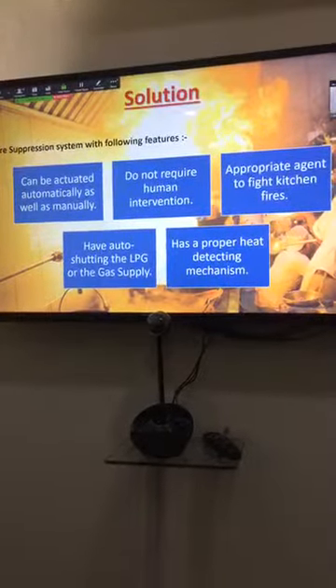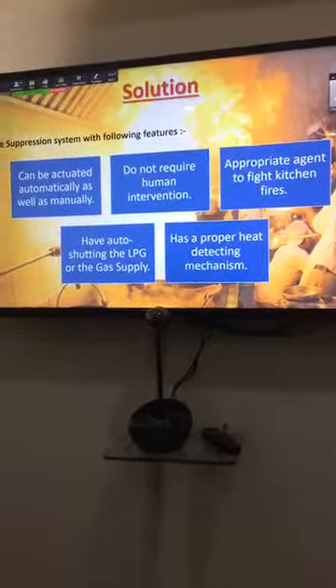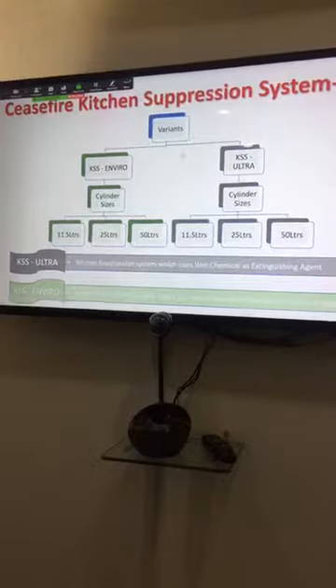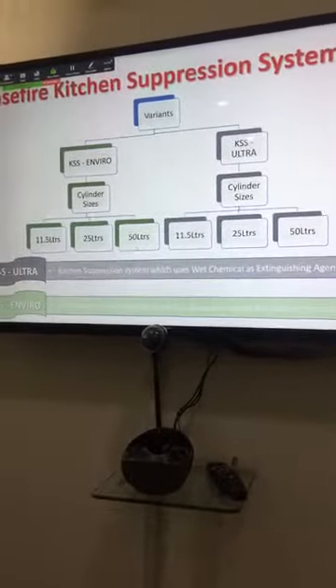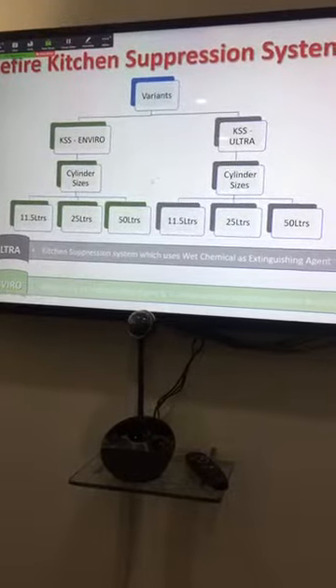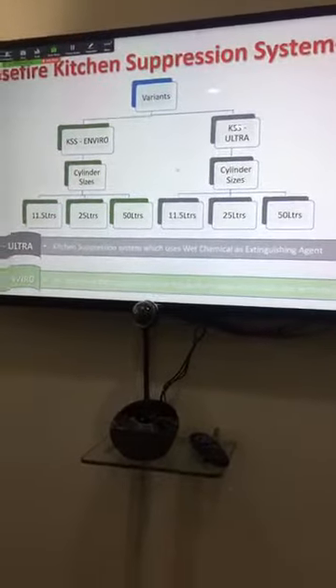With water mist, as you will see during the live presentation at the end of our meeting, it is pure and generates absolutely no collateral damage. We can protect different kitchen sizes depending on the application, from 11 liters up to 50 liters and even double that size. The supply unit can be situated outside the kitchen, up to 11 meters away from the protected unit, not creating any problem for the kitchen equipment.